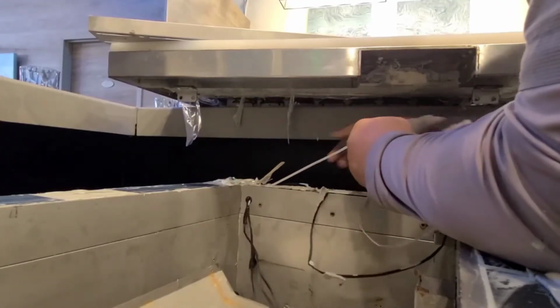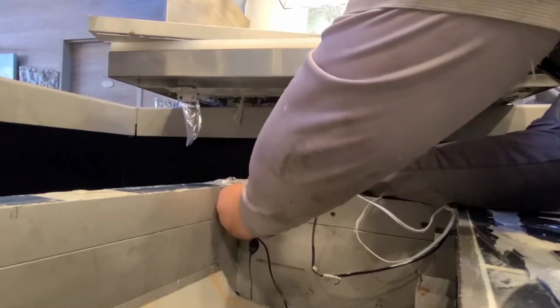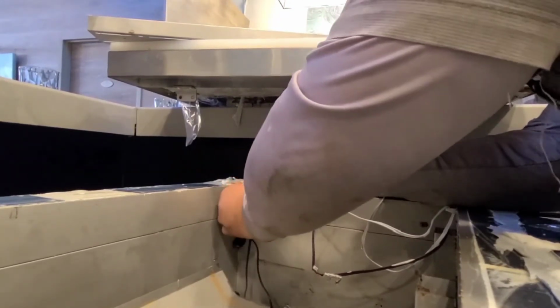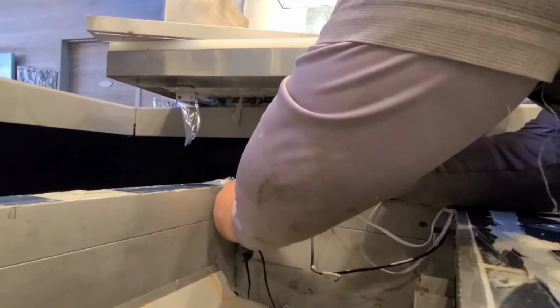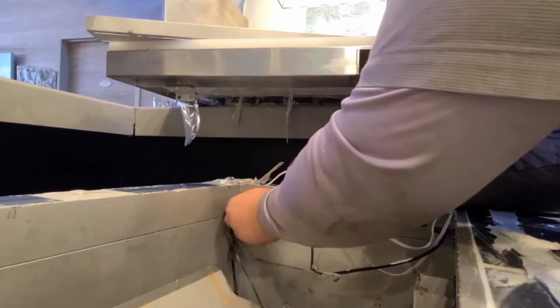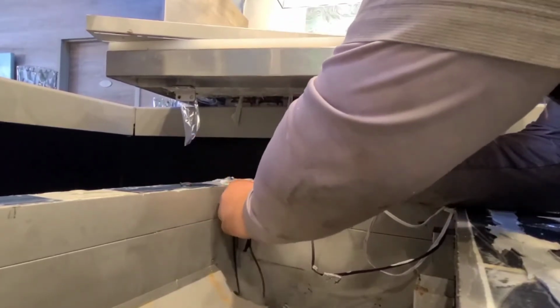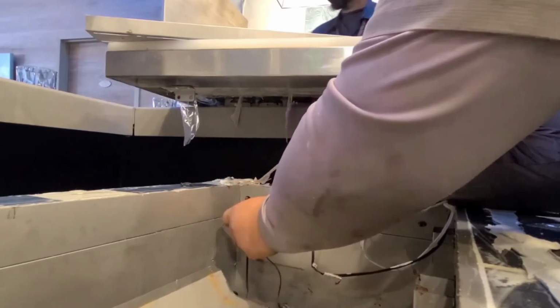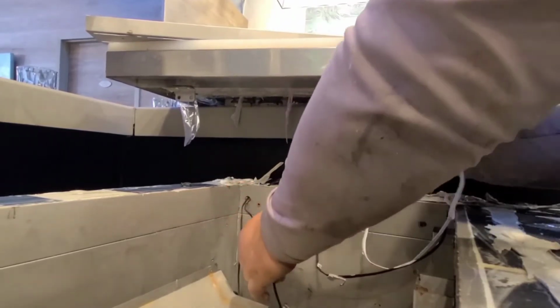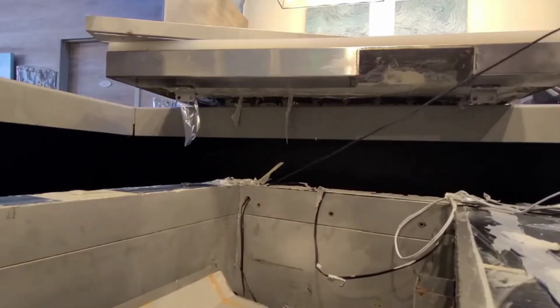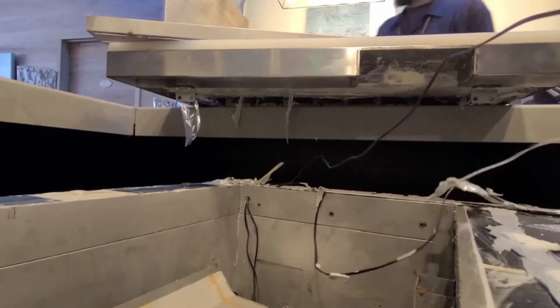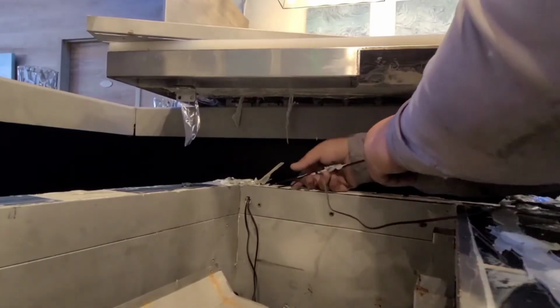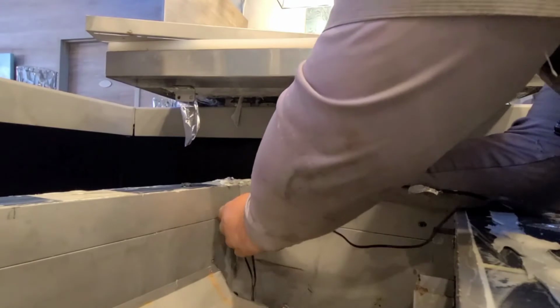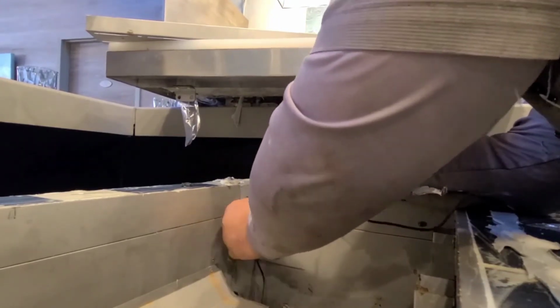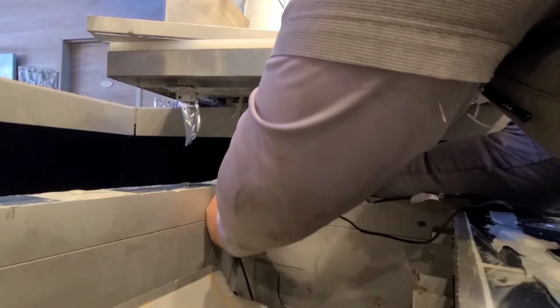So I'm just trying to get the sensors ran through one by one. I got it electrical taped to the new sensor so I could just pull it through the hole. And if you notice, I got a little tab on it, another piece of electrical tape on that one. That's just to help me remember that that one is for the room temperature sensor. So that way I don't get confused as to which one's which when it's ran through. Especially since they're both black. Before it was a white sensor and a black sensor, now they're both black. So that's why I got a little piece of electrical tape on the end there.